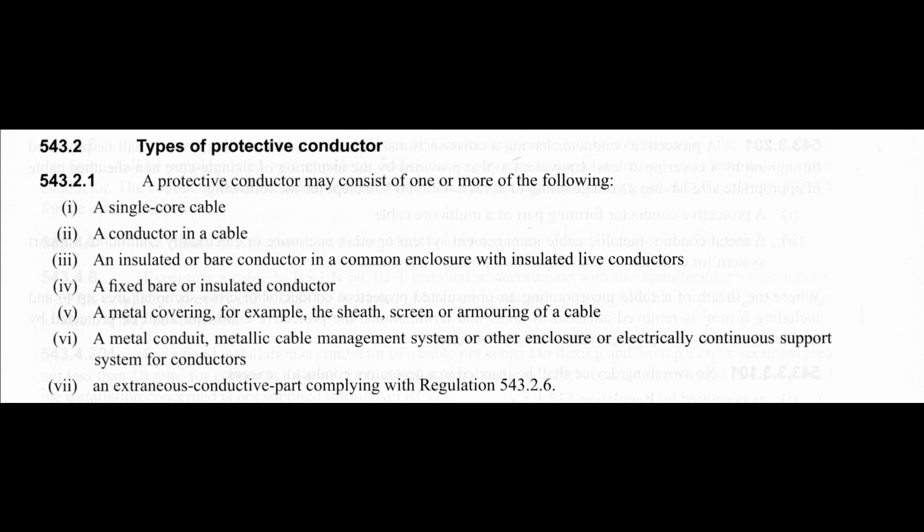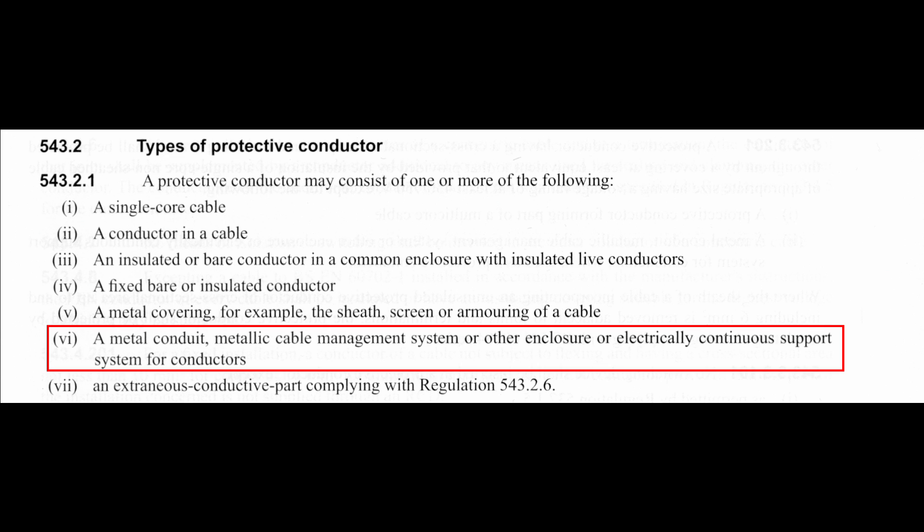Now let's have a look at the regulations which apply here. There are several of these, but the important point is regulation 543.2.1, item (vi), which clearly states that metal conduit is acceptable for use as a CPC. The next point is that you do need to put an actual wire from the terminal of each accessory to the earthing terminal in the conduit box.